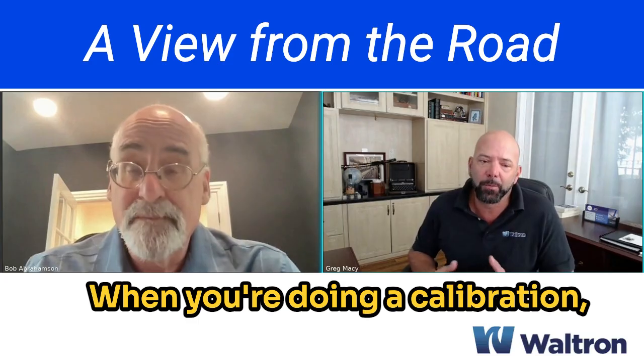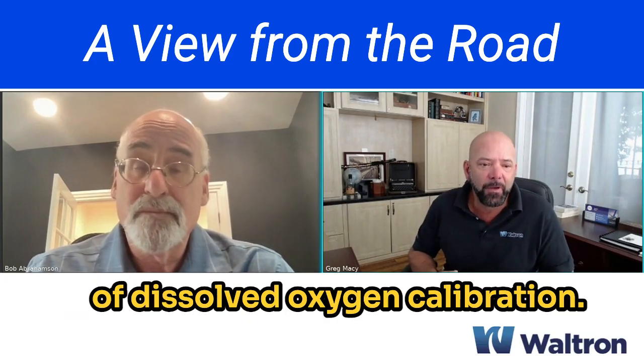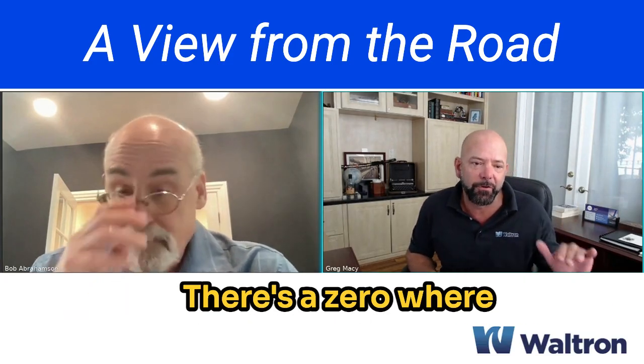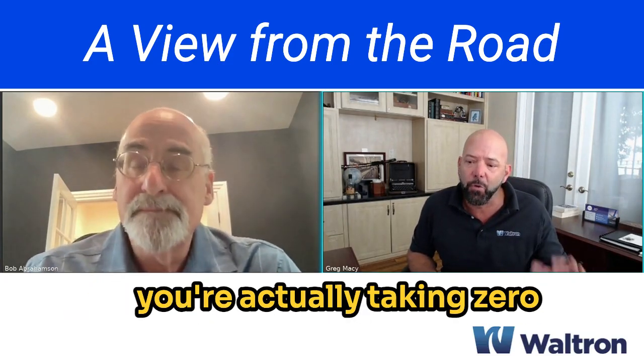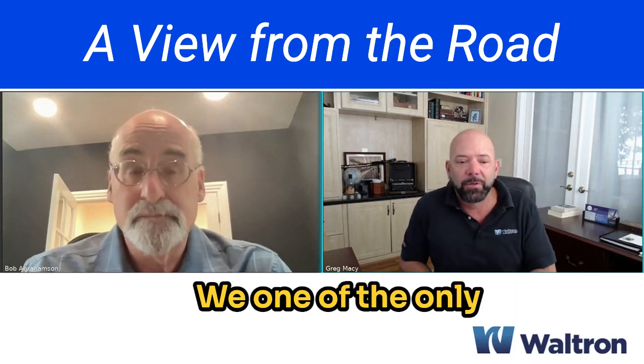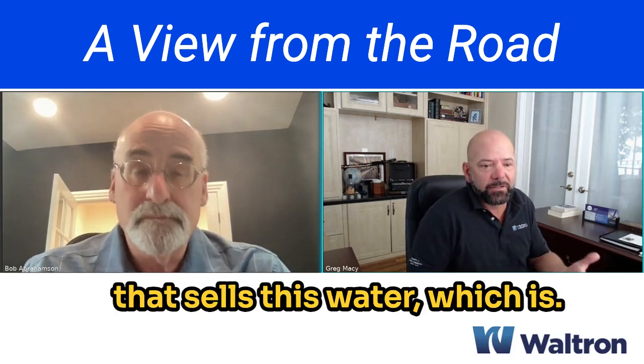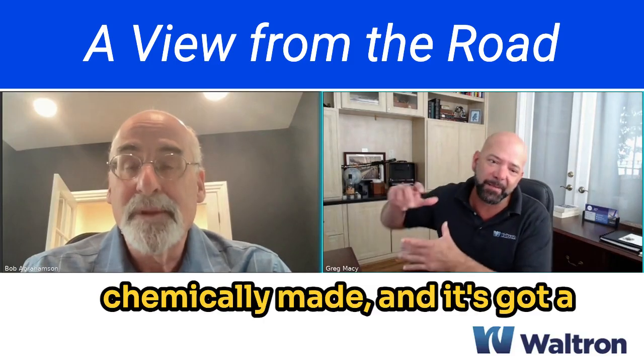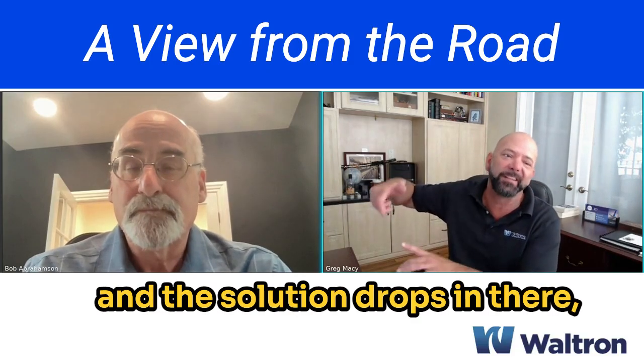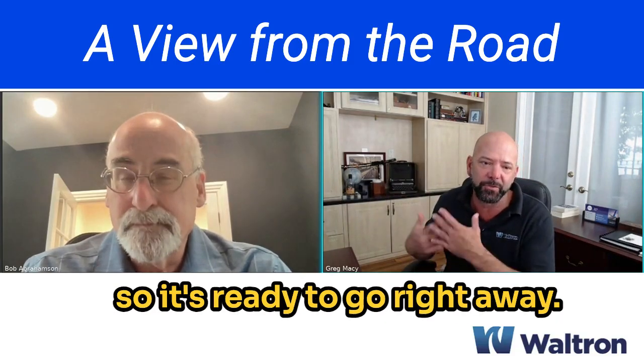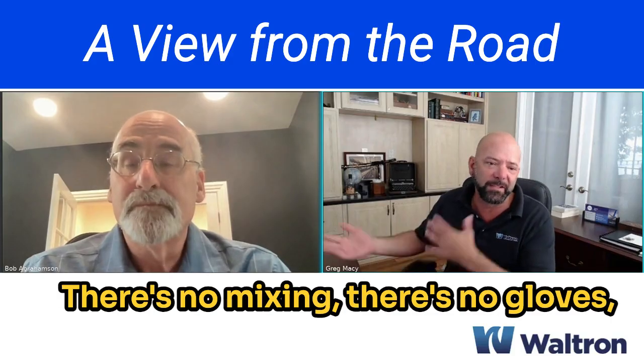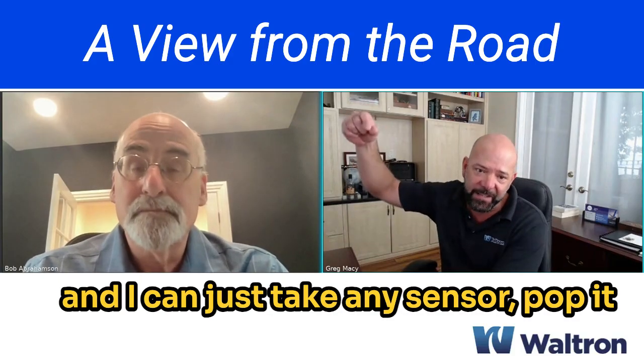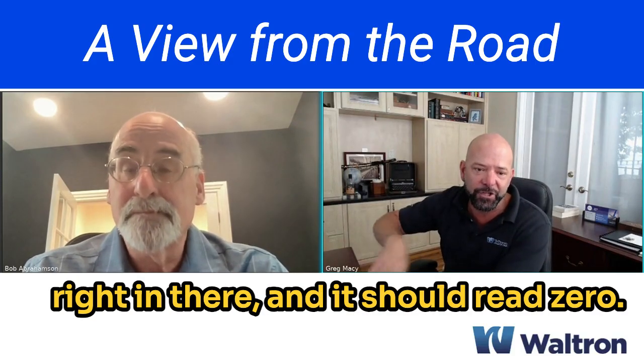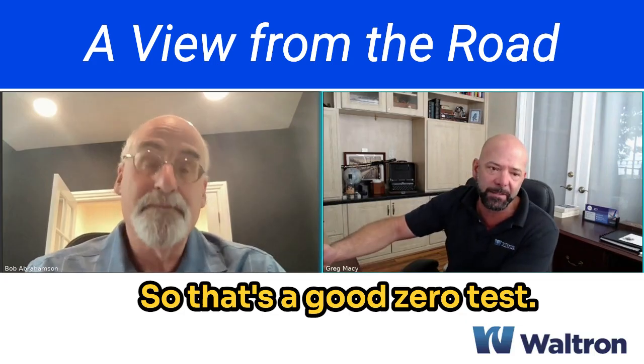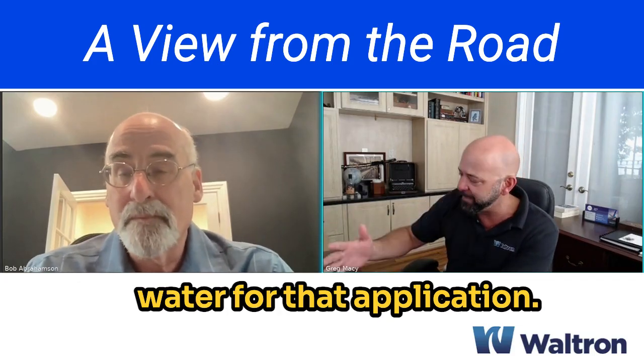Okay. When you're doing calibration, there are 2 types of dissolved oxygen calibration. There's a zero, where you're actually taking 0 water, which Waltron sells. We're one of the manufacturers in the industry that sells this water, which is chemically made, and it's got a beautiful cap that you just turn and the solution drops in there. So it's ready to go right away. There's no mixing, there's no gloves. I can just take any sensor, pop it right in there, and it should read 0. So that's a good 0 test. We have the 0 water for that application.